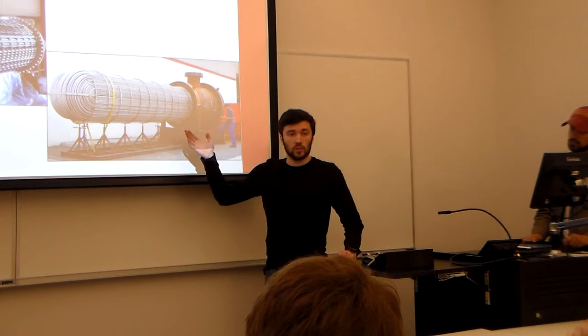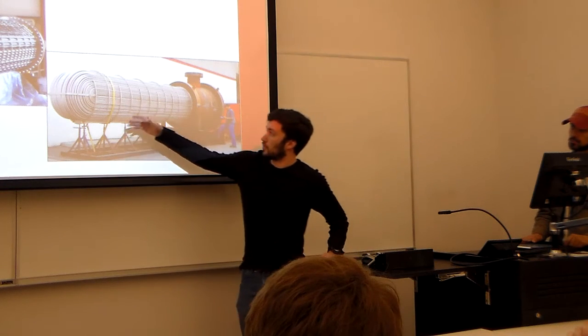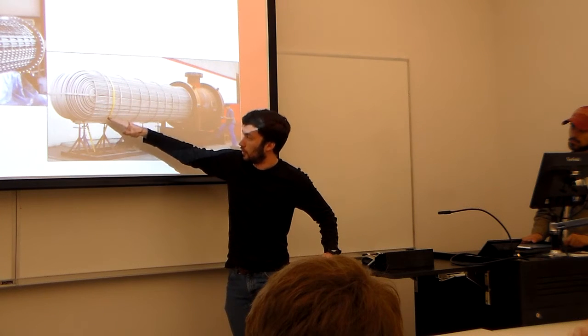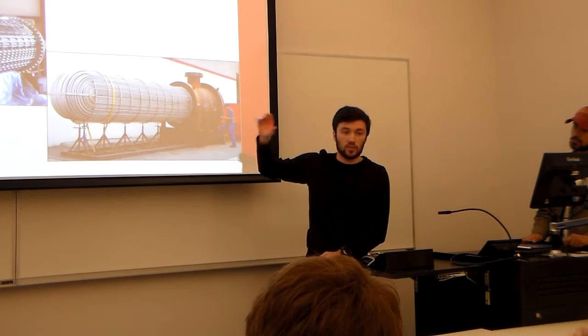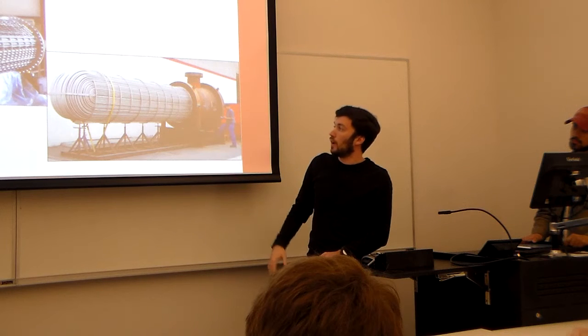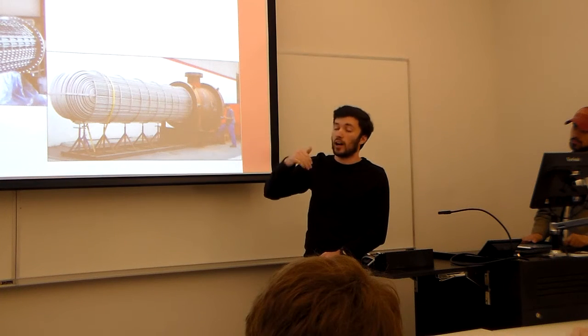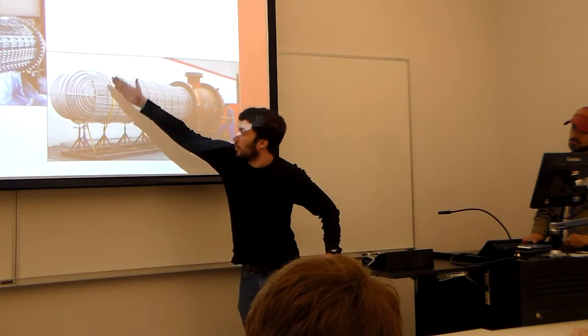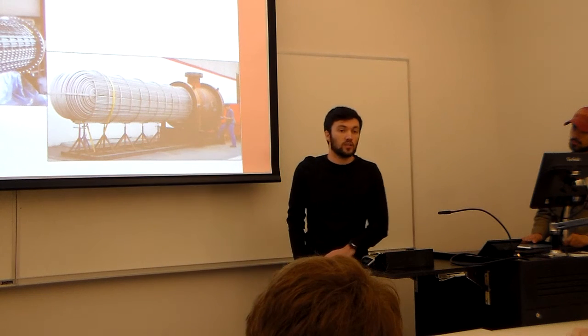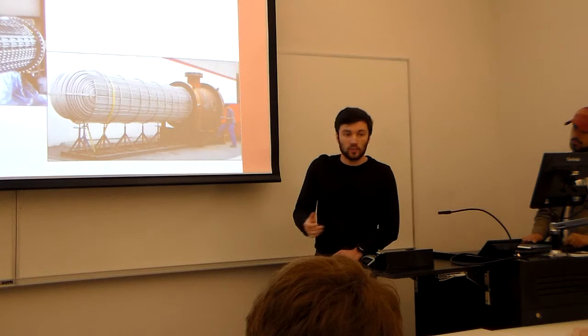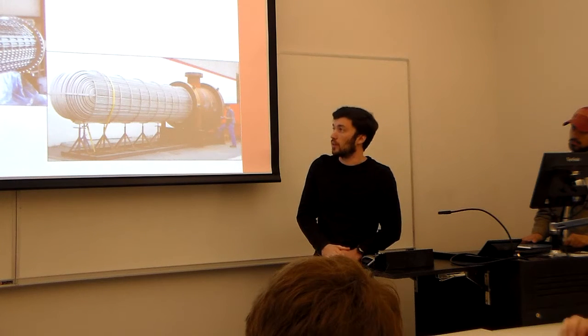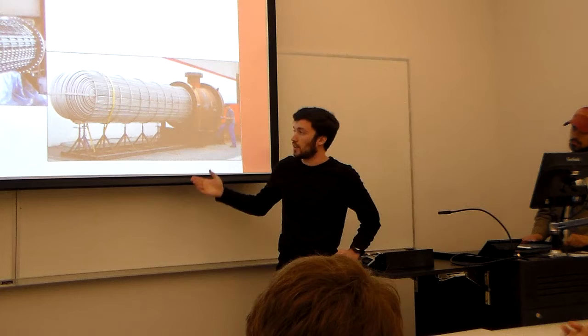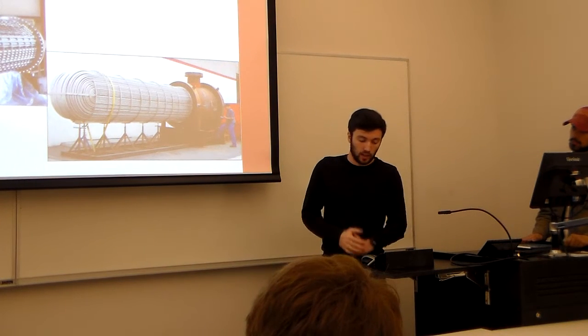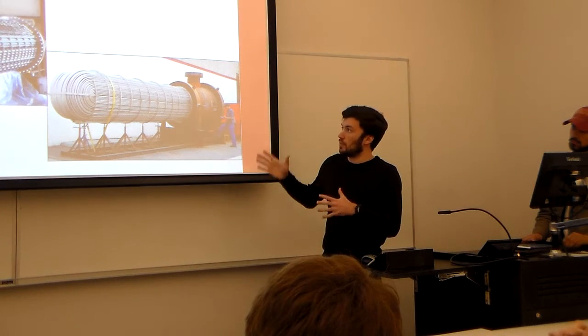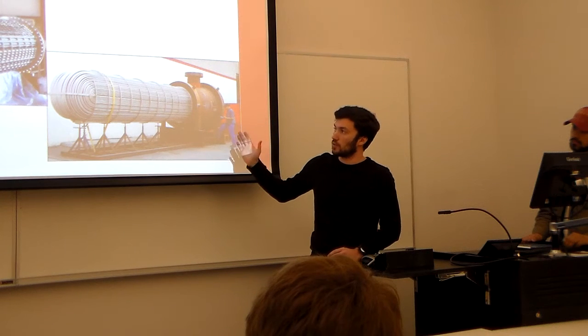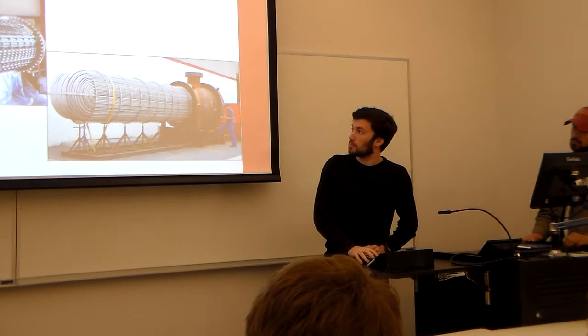This here is an actual U-tube heat exchanger, and you can see that the baffles are different because they don't actually go up to the top and all the way to the bottom in each case. That's because the shell that goes over these tubes has the hot liquid flowing over, and it will go up and down between these baffles. So it's actually a cross-flow heat exchanger. You may have learned about that in heat transfer, you may have not. This is used because it has a high efficiency. It can take up a lot less space, and having a string of these really allows the efficiency of the whole plant to be increased.